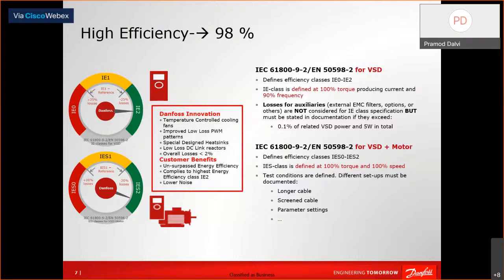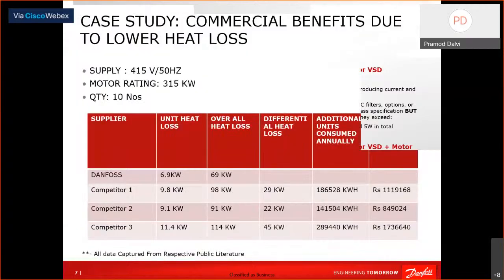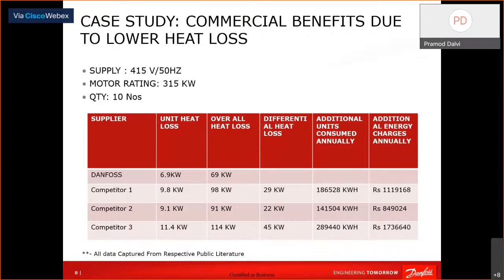With this, the customer benefits with the best compliance, first the compliance of IEC, and second the commercial benefit also. The next slide shows one example. If you have ten 315 kilowatt VFDs in your plant with Danfoss as the supplier, the unit loss of a 315 kilowatt VFD is around 6.9 kilowatt, so overall 69 kilowatt. But with other multinational brands, the heat loss is a bit higher, and the difference, in the third column, is around 29, 22, and 45 kilowatt for the same rating.